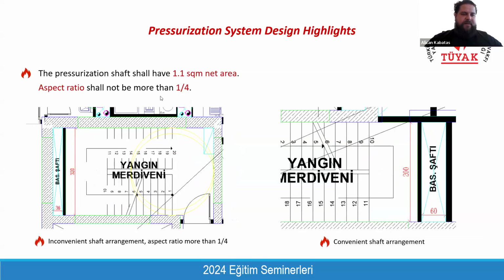And also, as I stated, the required area for the pressurization shaft is about 1 to 1.1 square meters. And the aspect ratio is also important. It means the ratio between the length and width of the stair shaft. It should not exceed 1/4, because otherwise, even if you provide 1 square meter, the shaft will not work as required. It will cause a lot of pressure drop and the system won't work. That's why while designing a shaft, it should not be very narrow. It should not be very wide. The aspect ratio should be kept between 1/3 and 1/4 so that it can work as required.